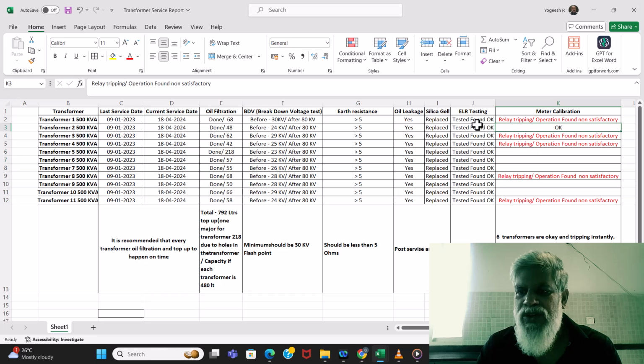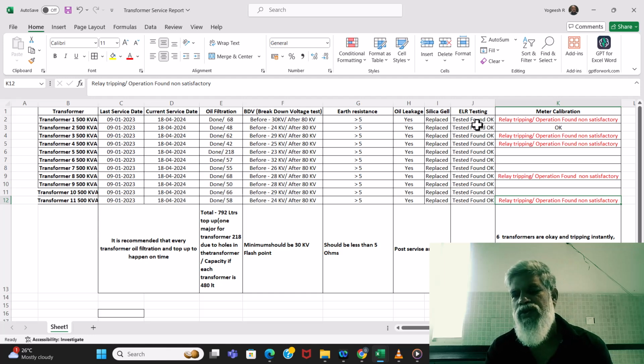Now coming to meter calibrations, transformer 2, 5, 6, 7, 9, and 10 are functioning properly. So that means it is tripping the moment there is some kind of anomaly. However, transformer 1, 3, 4, 8, and 11 are not tripping immediately. We need to make multiple attempts for it to trip. So that's something that we want to look into. And a different vendor is required who will test and replace the control system that is required. Now, what does this do? Generally, this trips whenever there is any kind of anomaly.